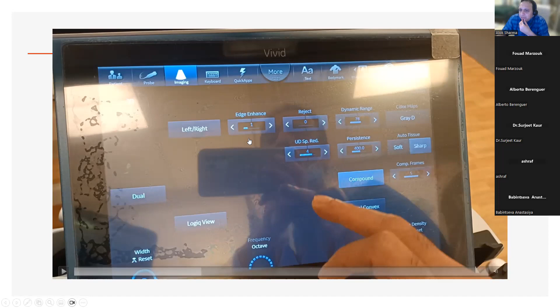By increasing dynamic range, you're increasing the ability of these ultrasound waves to penetrate beyond the pleura. Naturally, if the ultrasound waves can penetrate beyond the pleura, they're going to interact with deeper tissue better, and you're going to get better depth analysis and better interpretation of the tissue and artifact that's deeper. So if I'm looking at a deep consolidation, and I'm not getting good pleura, and I'm trying to debate whether this is a consolidation or artifact, I might increase my dynamic range. But I might decrease my dynamic range if I'm trying to interrogate just the pleural area. Alternatively, I might just want to increase my frequency. So there are multiple ways in which you can help yourself. But there's one more thing that is very important.